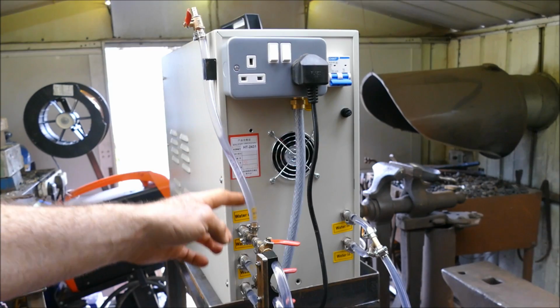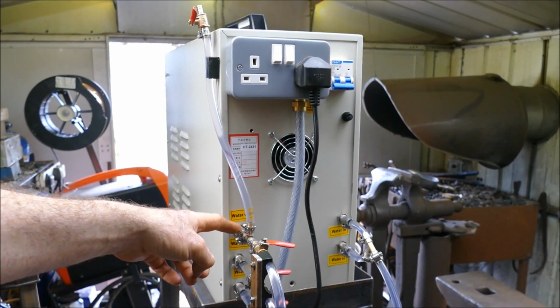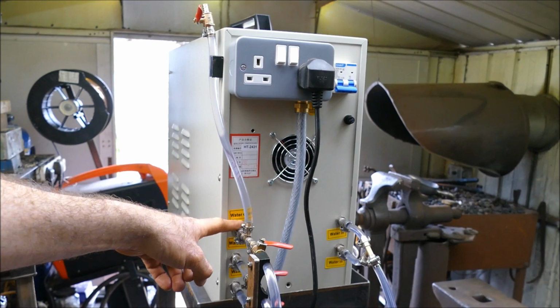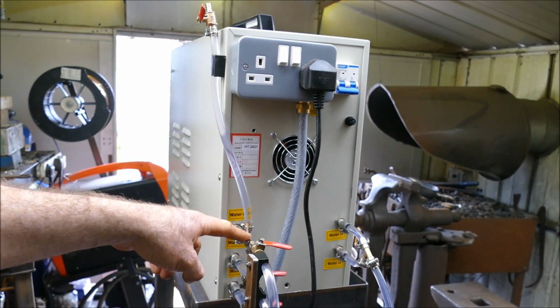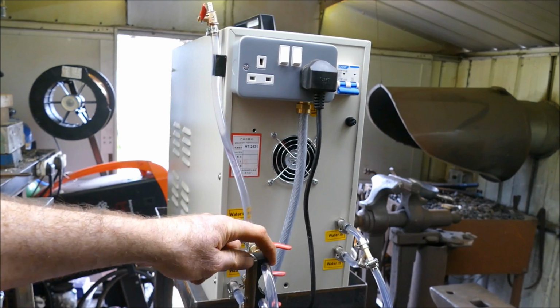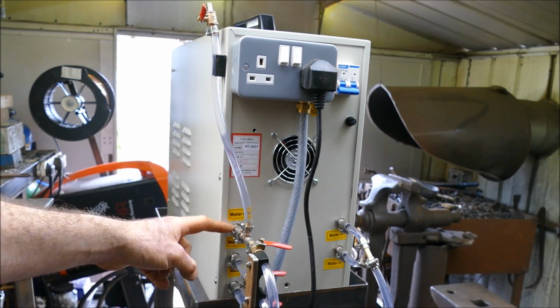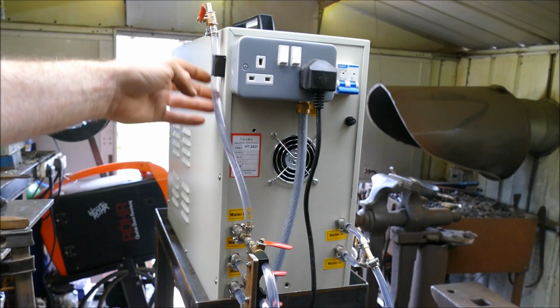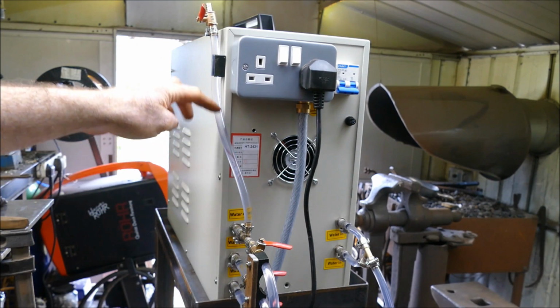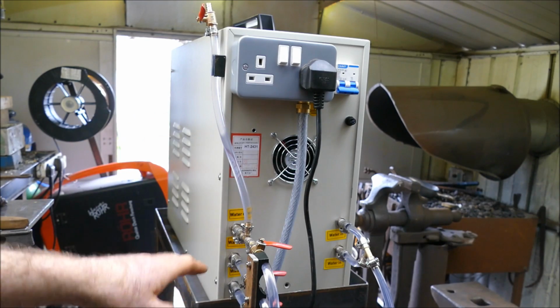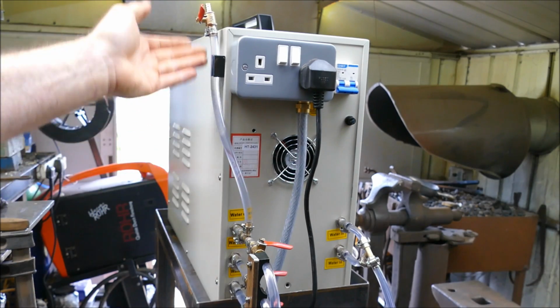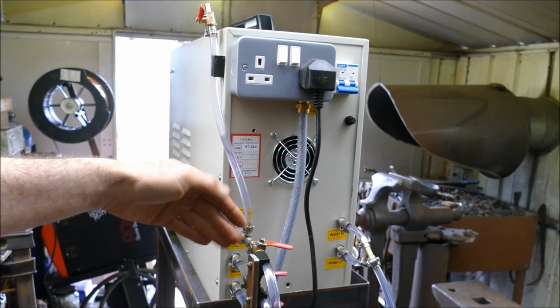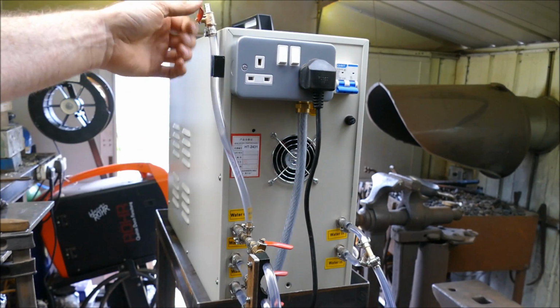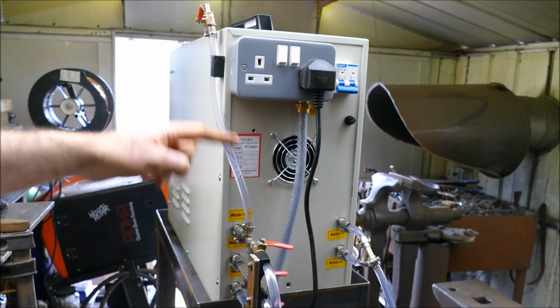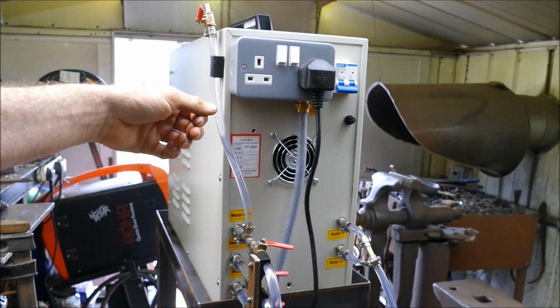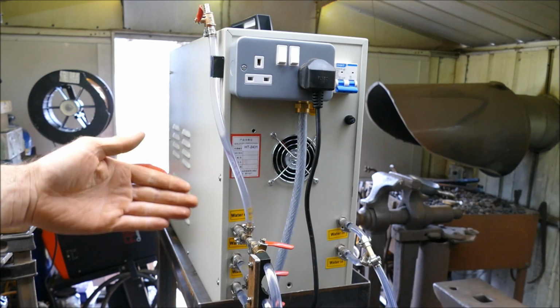Right, so this pipe here, basically what happens if there are any air bubbles that form inside the machine, they tend to stay at the top here, and they don't recirculate back down, which can cause a pressure issue again. So what I've done is I've just created this pipe here with a valve at the top, and that allows bubbles to flow up and then stay here, keeping the rest of the machine fully purged. And to get rid of the air completely that fills in here, I switch off all of the valves here and open this one. This allows water to circulate just through here only, all the air escapes. I then turn it off and the system is fully purged again.